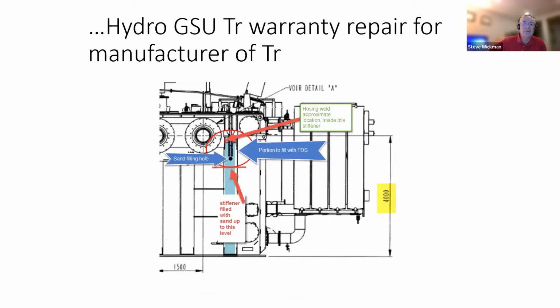This was a fun adventure. This was a huge GSU transformer at a hydro plant up in northern Ontario, I believe. And the manufacturer had an issue shortly after this unit was installed, that they had a weld fail actually inside this vertical stiffener. And their traditional repair would have been to find a way to take this unit out, take it apart, and re-weld that area there, which is a logistical impossibility.